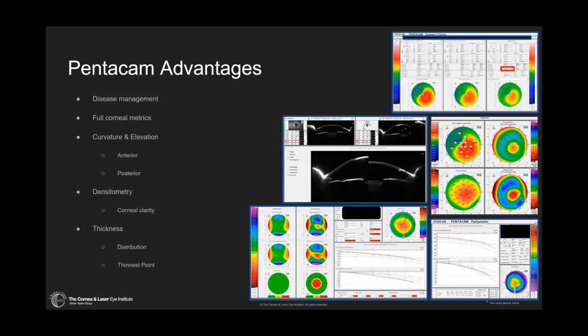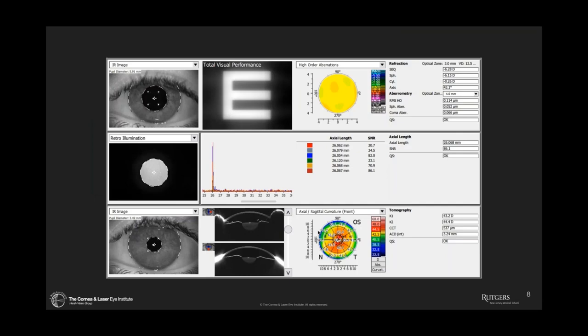We're getting full corneal metrics on these individuals from the Pentacam: anterior curvature and elevation, densitometry — the measurement of corneal clarity — shape and profile via Scheimpflug images, sagittal depth, thickness and thickness distribution. We can also look at really cool artificial intelligence in the device for screening metrics to find keratoconus and risks for corneal ectasia at a much earlier stage.